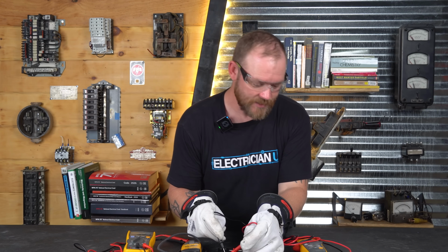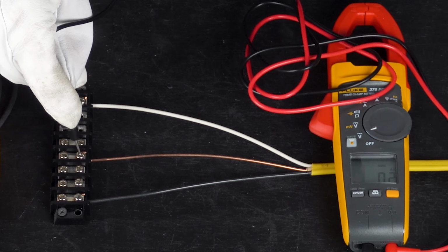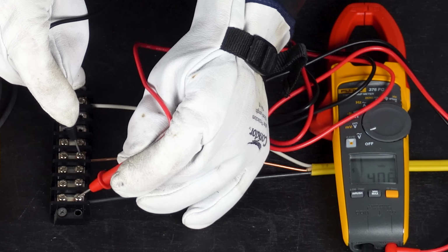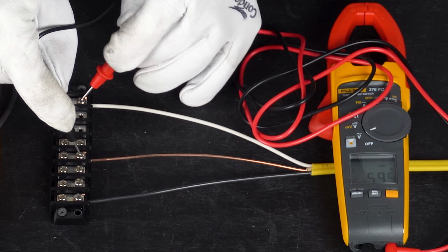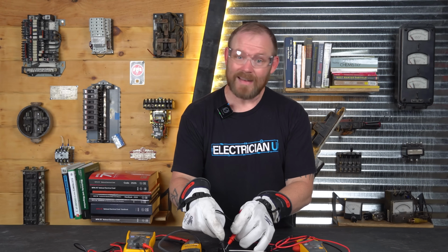But once I go to a conductor that's not hooked up to anything and I get a voltage, this shows 52.2. Sorry, I'm looking upside down so you can see the numbers. But what is 52.2? That conductor's not actually hooked to anything. So why is there a voltage there? Well, it's a ghost voltage. If I go between neutral and bare conductor, I get 59.5. Again, ghost voltage, not real voltage.